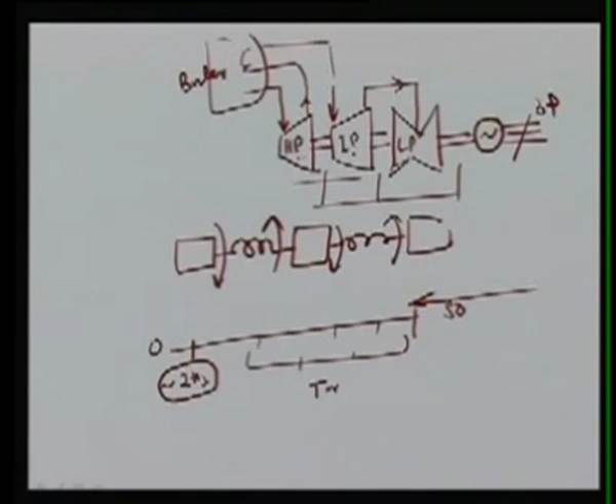Now let us go back to the various stability phenomena, defined as transient stability. As already discussed, small signal stability means small disturbance stability concern. Transient stability is also known as large disturbance stability, and it is the ability of the power system to maintain synchronism when subjected to a severe transient disturbance. Severe meaning it may be a 3-phase fault, severe power outage, other types of faults, or tripping of a severely heavily loaded transmission line, then transient stability phenomena will occur.